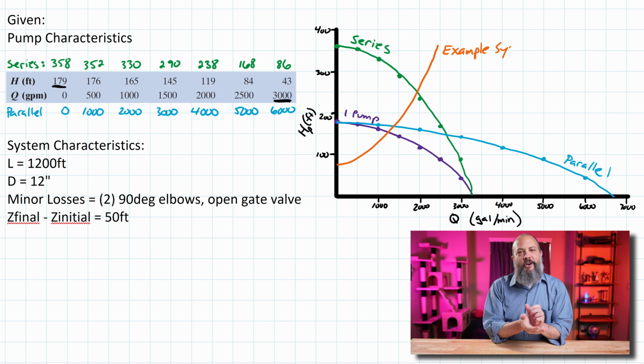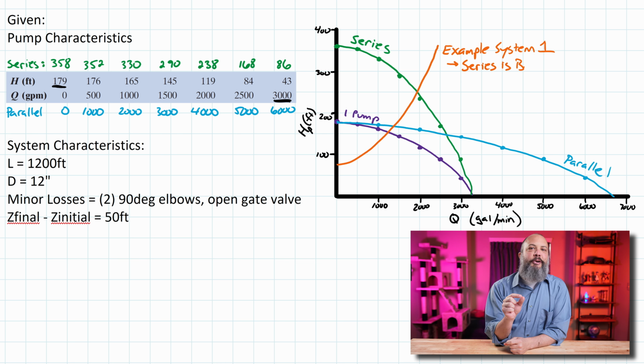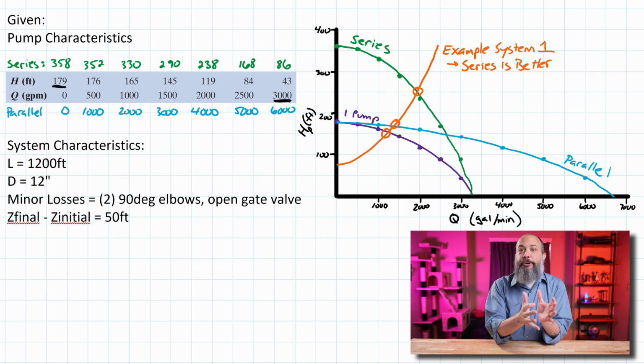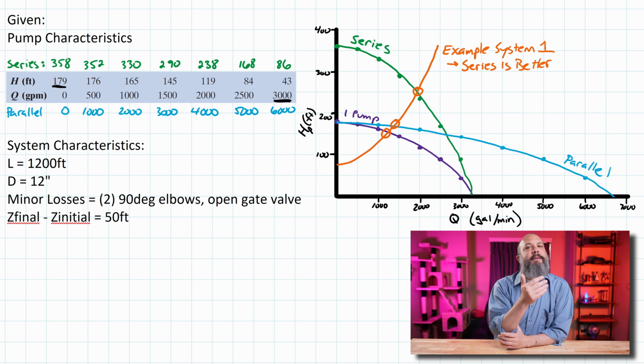If your system curve is very tall and steep, sort of like example system 1, then you'll notice that the point where the system curve and pump curve crosses the series set of pumps is up and to the right of the parallel. This means series would be better. You'll get more flow rate at a higher pump head using two pumps in series. And in fact, for a very steep system curve, the parallel actually performs almost the same as having just one pump. It really would be a waste of money to go from one pump to two pumps in parallel. Those intersections with the system curve are almost right next to each other.